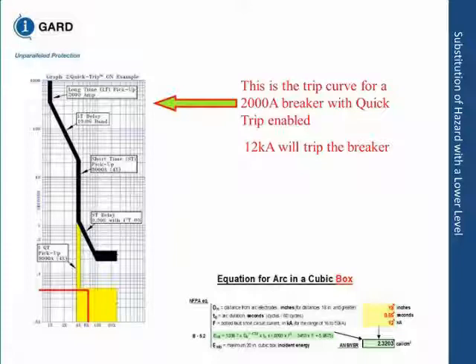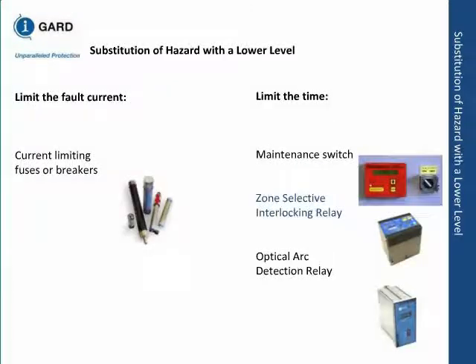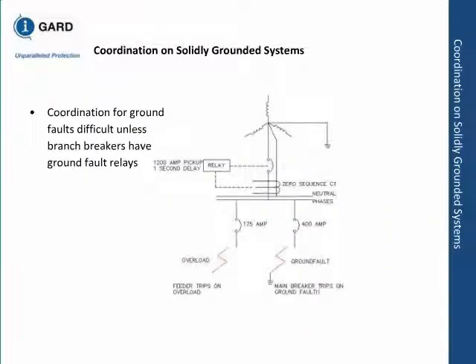Other technology, zone selective interlocking. Like I explained to you, when we have two devices in series, we cannot set both at instantaneous. So the upstream main breaker is normally set at short time, and the feeder breaker is set at instantaneous. What does zone selective interlocking do? This is basically a smart system. If the fault happens downstream of this breaker, these are all interconnected. This device is telling the main breaker, I see the fault. I will clear it. So you hold on.